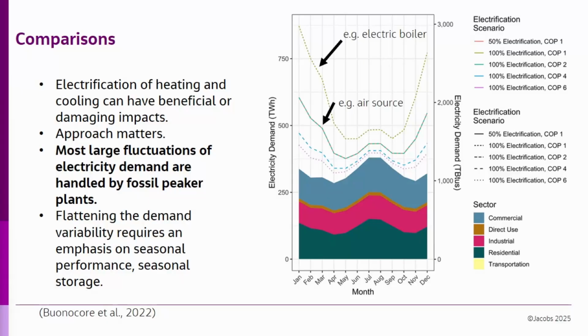If we can implement geothermal energy networks and achieve more passive heating and cooling opportunities with load sharing across our cities, our coefficient of performance can increase from a COP of 1 for the electric boiler up to about 6 to 14 for most systems measured so far.